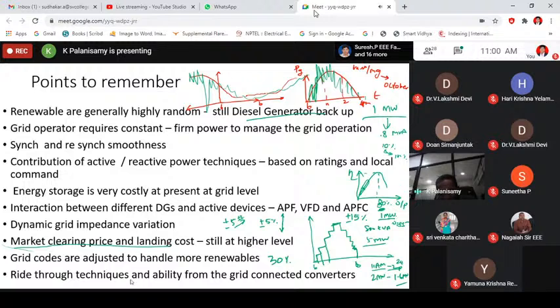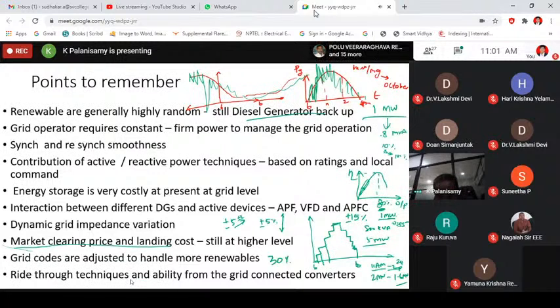This was the case. But now the recent grid codes are saying that if the fault is in your premises, or close to your place, the grid and the conventional sources will supply the fault current anyway. What the grid code is saying is that you also should support the fault current. Earlier the entire current was supplied by the conventional generators, but now, as per the recent grid code, you also should contribute fault current. It means that if the fault is very close to your point, you stop your active power injection and start to increase the current. For a short time you can even increase the current beyond the rating of your inverter, maybe 120%, something like that. So you have to supply the fault current throughout the fault clearing period.